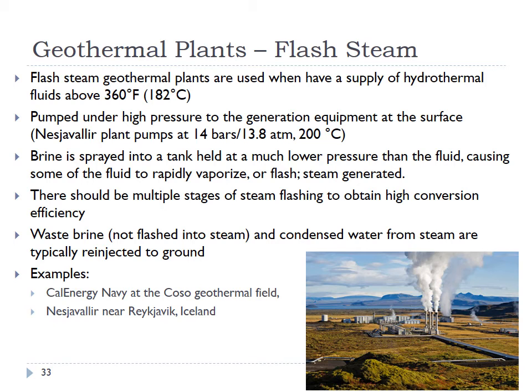So that's what we mean by flashing. Some of the liquid goes into the vapor phase, which is endothermic, cooling the temperature of the liquid, but generating some steam. Often these types of power plants have multiple flash tanks at different pressures - maybe you go from 7 bar to 4 bar to 1 bar, those kinds of orders of magnitude. At each stage, you're pulling off a little bit of vapor, and the temperature/pressure from which you're pulling it starts dropping as you go down those flash tanks.